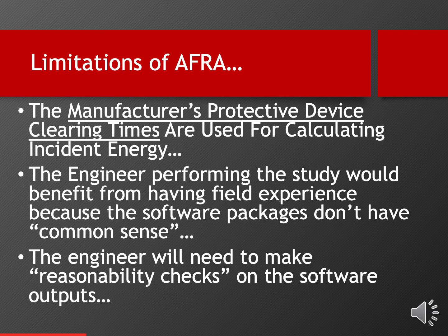So very important point on the slide. It would benefit if you have engineers who have a field background, meaning they've actually done work for a living, for example, like an electrician or electrical technician of some kind, or at least had worked in an environment where they work with workers, because there's a lot of interpolation that needs to happen with the study. And it helps if you have a background to do kind of a common sense check there. And that's really the last point, the idea of a reasonability check on the software outputs. Most of the time, the software does an excellent job. There are a few times when you'll get an anomaly, and you have to have enough experience to notice that just by looking at the data. Let's go to the next slide.